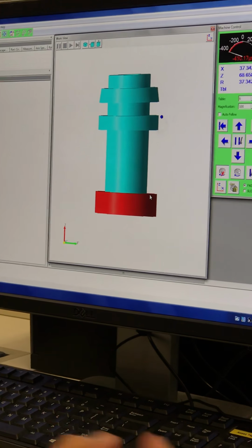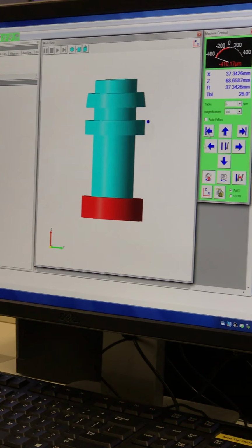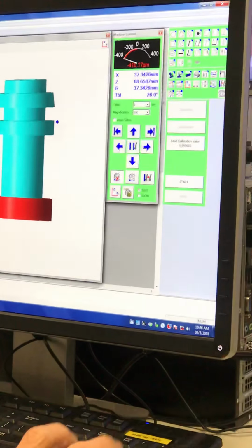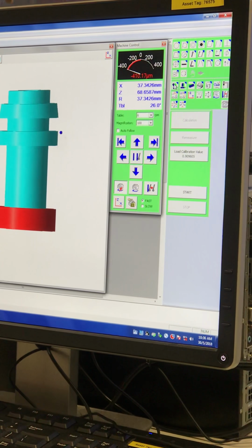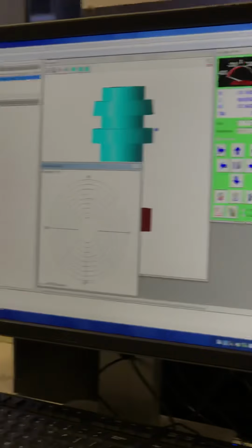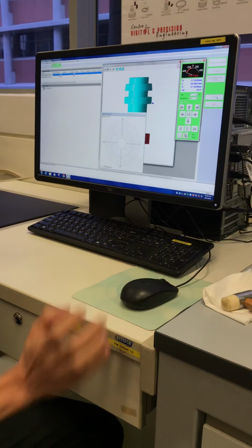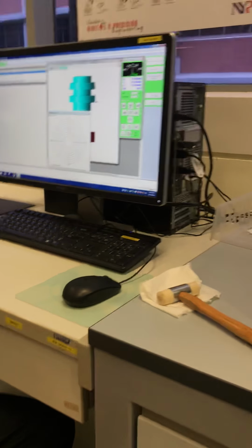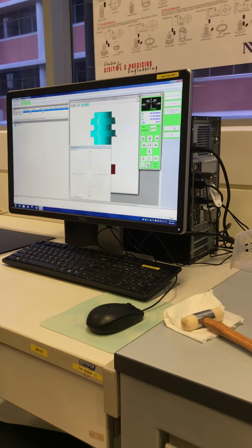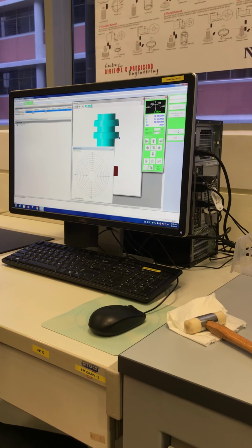Then what else? Press the centering and leveling to start the process. Press means this button here. Same icon, press is to start. Move the stylus to the first element. Press start. So now it will do the alignment for us automatically.